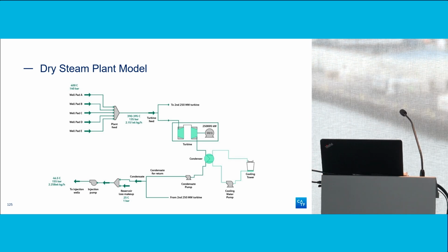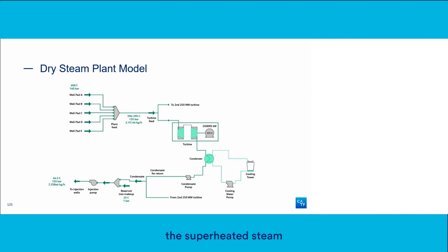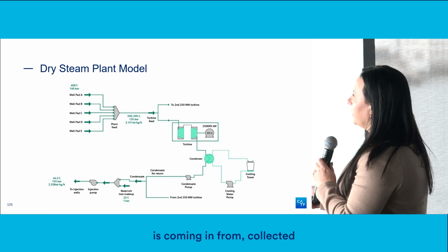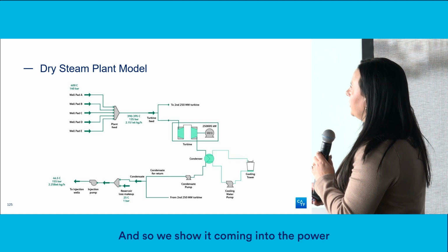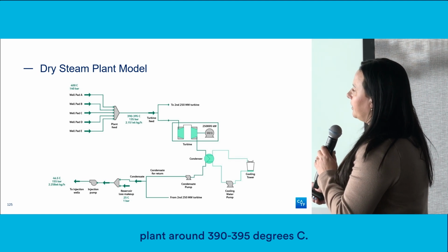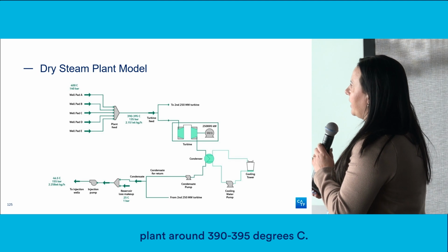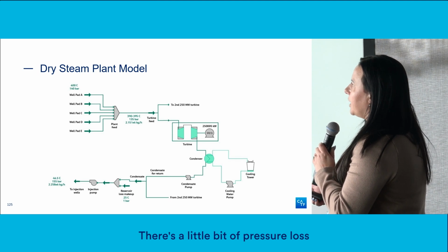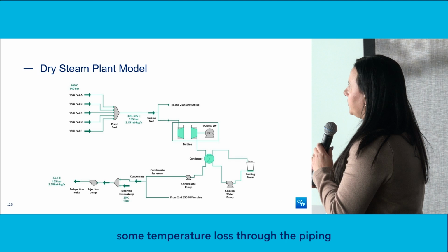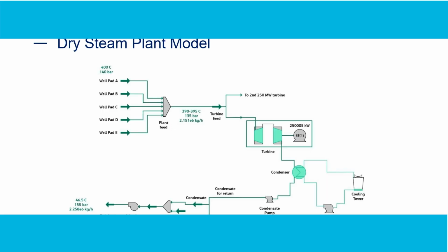So the superheated steam is coming in, collected from all those well pads. We show it coming into the power plant around 390 to 395 degrees Celsius. There's a little bit of pressure loss and therefore some temperature loss through the piping.